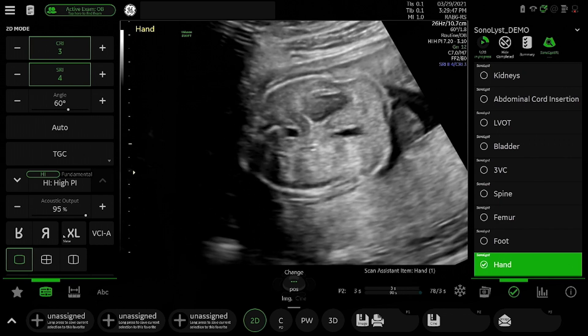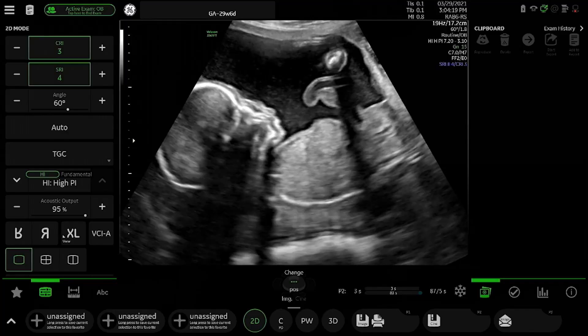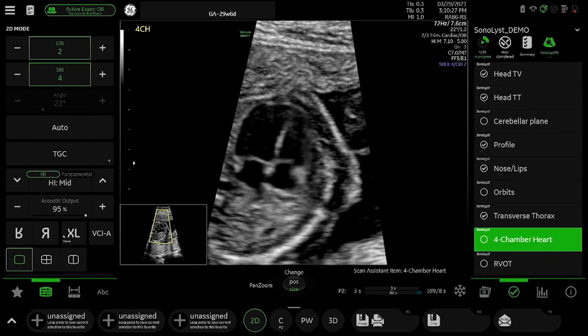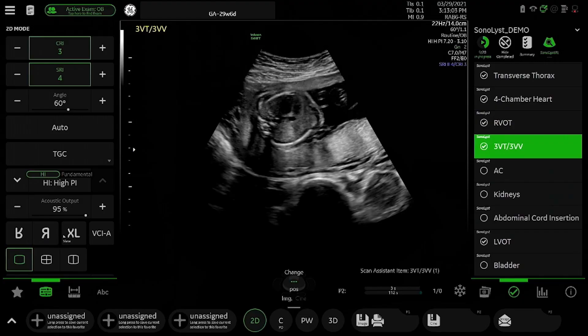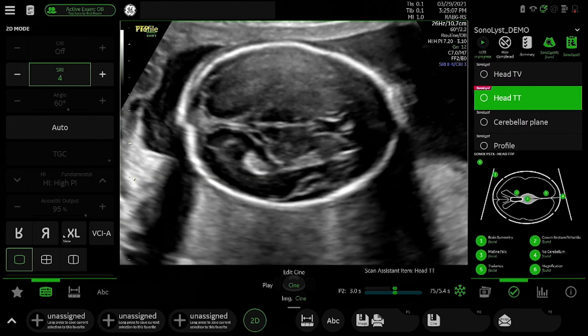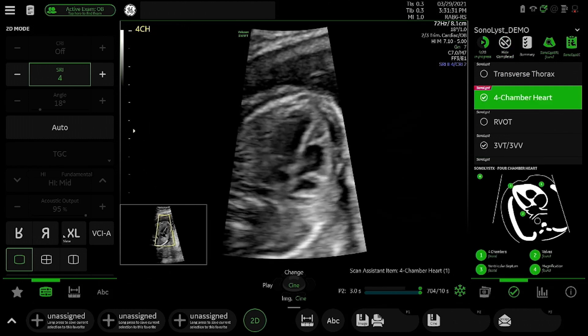The way that SonoLyst works — it's an AI algorithm, an artificially intelligent algorithm — and it works by a process called deep learning. What that involves is showing a computer thousands and thousands of ultrasound images that have been carefully curated by a pool of expert sonographers. On each image they have said this is what the image is and these are the imaging characteristics, and by looking at these thousands of images the computer learns essentially what you and I learn when we first do ultrasound. After being trained on a large number of images, it's able to tell the difference between, for instance, the transventricular view in the head and the transthalamic view in the head. Although these are quite similar in appearance, having seen enough of those pictures it's able to do image recognition and say no, it's this rather than that.